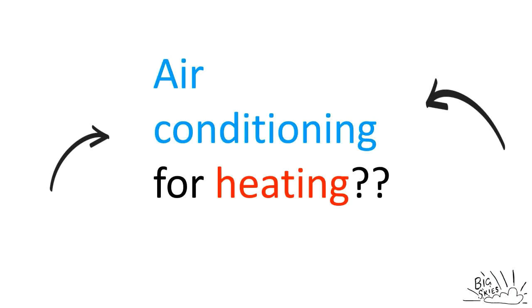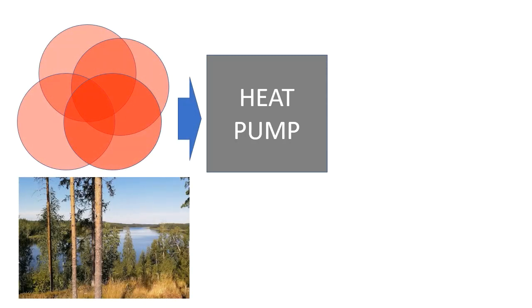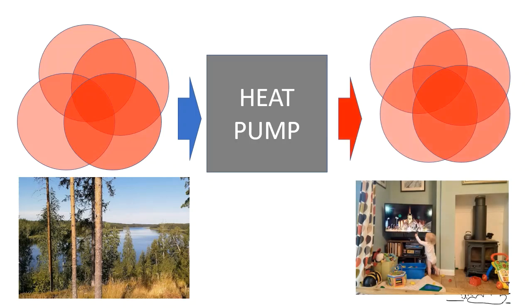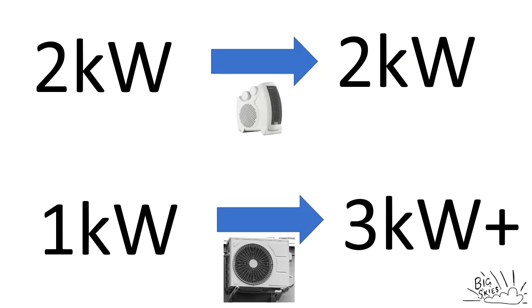Let's rewind slightly — how does air conditioning for heating work? An air conditioner is really just a heat pump. What heat pumps do is effectively take heat energy from one place — in this case outside — and transfer it to the inside. Even cold air, or what we'd consider cold air at zero or even below zero, still contains quite a lot of energy. Unlike a conventional heater that gives out a similar amount of heat energy to the electrical energy it took in, the heat pump is actually transferring energy and can give out more energy than it uses in electricity.